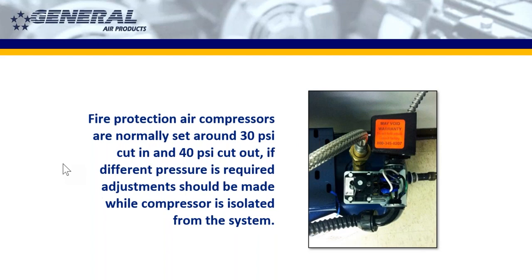Fire protection air compressors are normally set at 30 PSI cut in and 40 PSI cut out. Cut in means when the pressure switch will send the signal to the motor to turn on, and cut out is when the pressure switch will send the signal to the motor to turn off. While adjustments can be made, make sure the compressor is isolated from the system while you make those adjustments as best you can. So we always recommend that there's an isolation valve in line in the system.